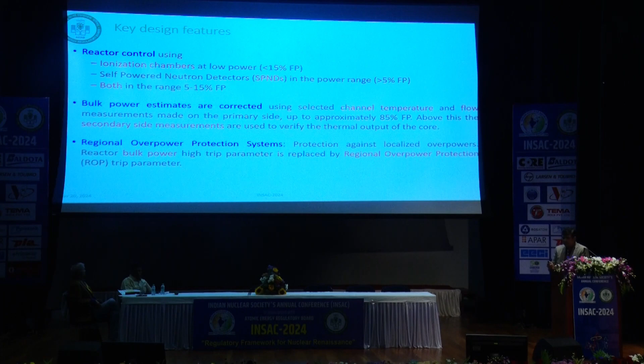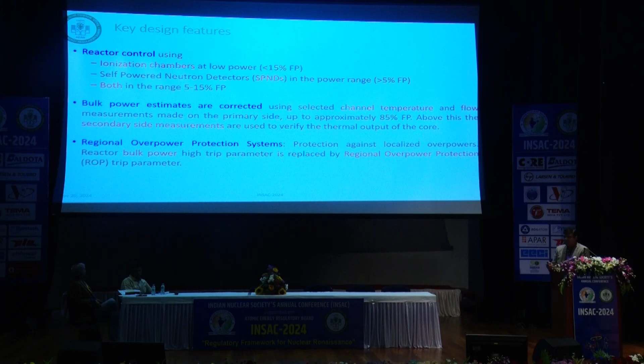Bulk power estimates are corrected using channel temperature and flow measurements made on the primary side. And there is a regional overpower protection system, unlike the bulk power protection system in 220 and 540 megawatt PHWRs.